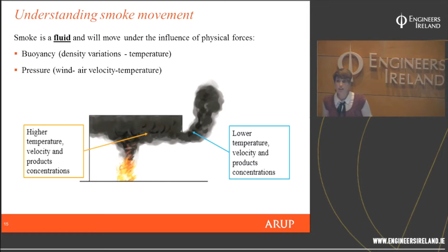In general, you have to take into consideration buoyancy - the variation of density of the smoke due to differential temperature - and also the action of pressure, which can be determined by wind, by air velocity within the building, and also by the ventilation system.